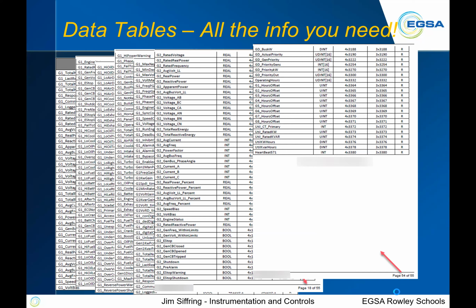So there is a lot of pages and a lot of data that's available if the ECU is able to write to those, and if your controller is able to see those different data tables, all that kind of stuff. So it's a place you can go. When manufacturers say J1939, the only thing common is the name J1939. The difference is that some manufacturers might use some piece of the data table and another manufacturer might use a different piece of that data table. They don't necessarily have to line up. So you couldn't necessarily take, say, a Cat controller and put it on a Cummins, because those two might be using different pieces of the data table, even though they're all still talking over that same J1939 protocol.